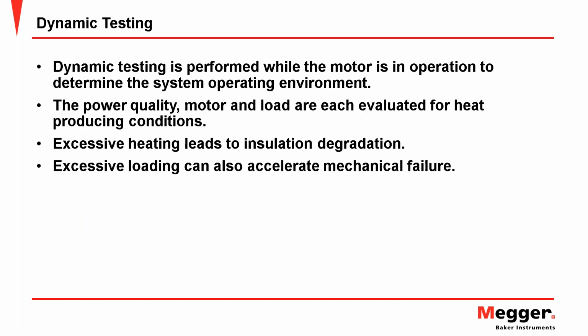Okay, and then the fifth test and the critical five is dynamic testing. I had a webinar last week where we covered an introduction to what dynamic testing is about, what kind of parameters it's looking at, how can it help us. Here are some of the highlights. Dynamic testing is performed while the motor is in operation, which is good because hopefully our motors are running more than they're not running. So there's a lot of opportunity to evaluate the dynamic condition. It evaluates the power quality, the motor operation and its response to that power quality, and the motor operation in response to its load as well. And of course, the load is evaluated.